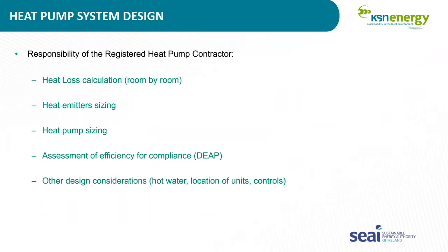They need to take a home and assess the heat loss in the home, room by room. They need to also assess the heat emitter in each room to ensure it can deliver sufficient heat at lower temperatures. They need to make sure that the heat pump is sized adequately, that it's not too large or too small, because too small and it'll be overworked and the efficiency will go down. Too large, same scenario will happen. SEAI wanted to keep it to maximum efficiency, optimum efficiency. They need to do that.